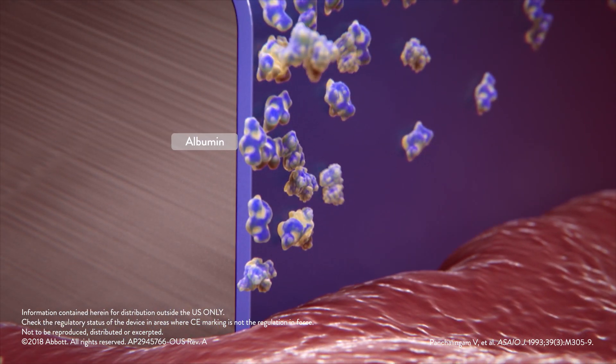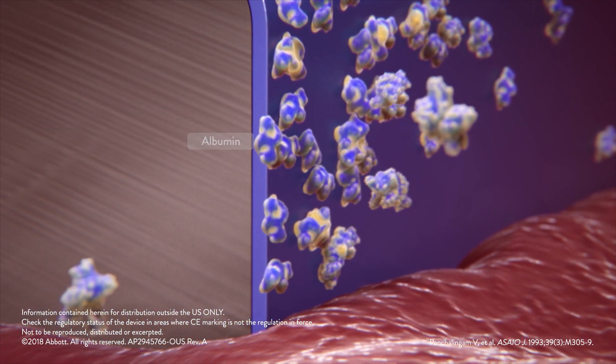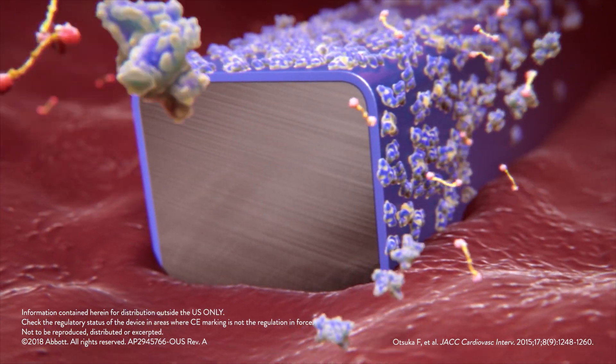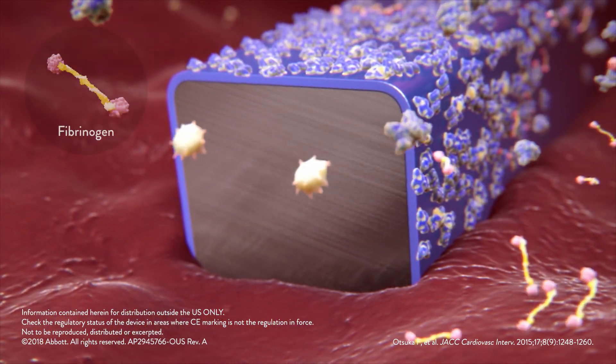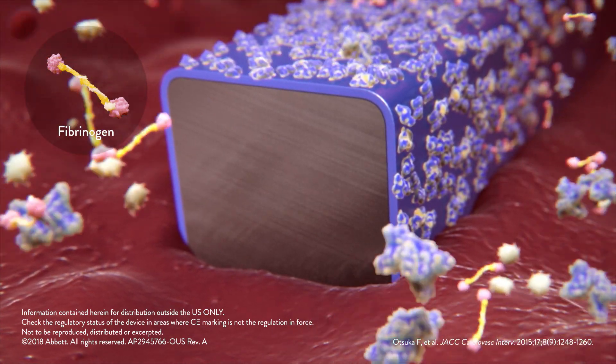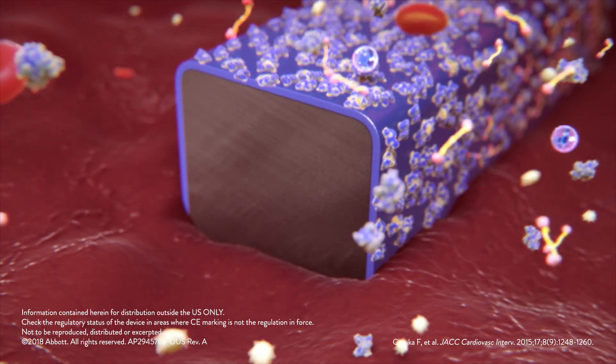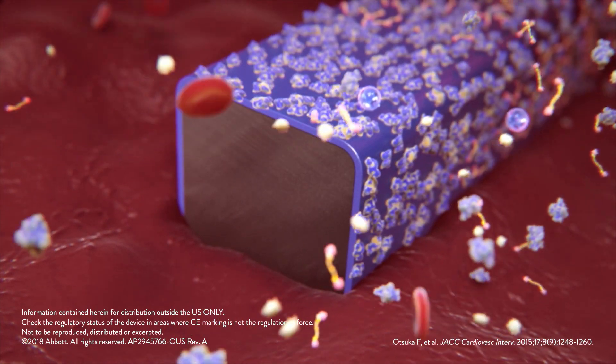a protective layer that masks and passivates the implant. The adsorbed albumin adheres and prevents fibrinogen adsorption, and thus provides thrombo-resistance.